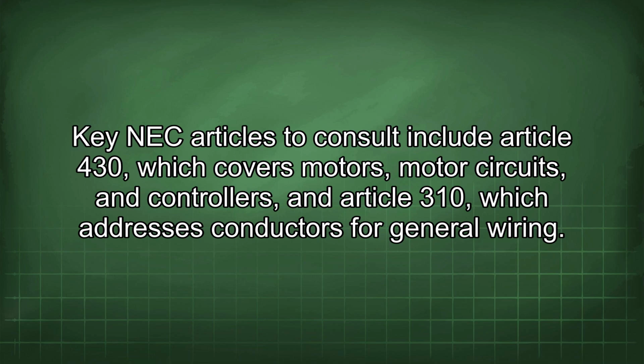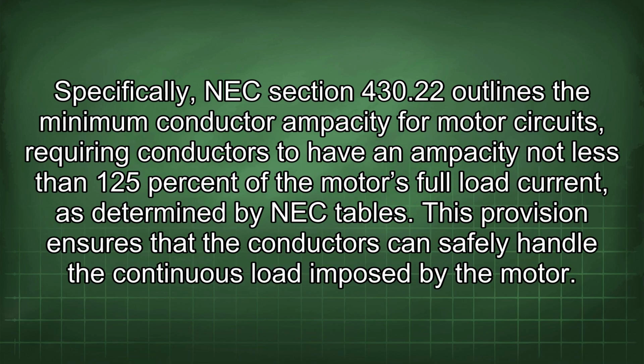Key NEC articles to consult include Article 430, which covers motors, motor circuits, and controllers, and Article 310, which addresses conductors for general wiring. Specifically, NEC Section 430.22 outlines the minimum conductor ampacity for motor circuits, requiring conductors to have an ampacity not less than 125% of the motor's full load current, as determined by NEC tables. This provision ensures that the conductors can safely handle the continuous load imposed by the motor.